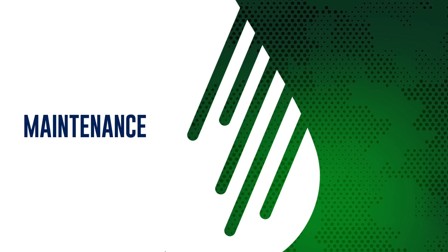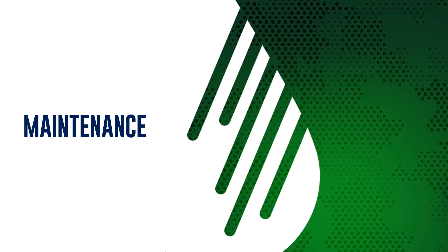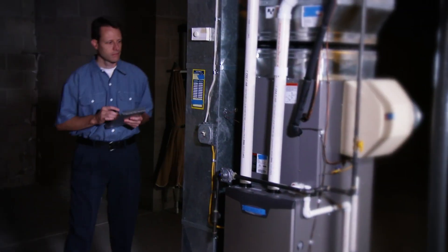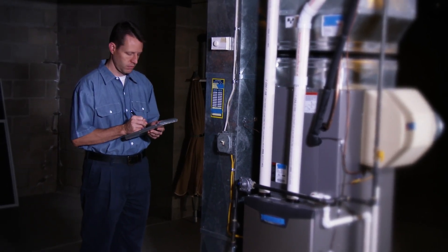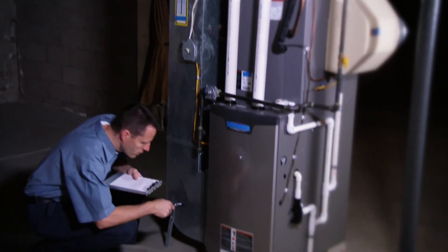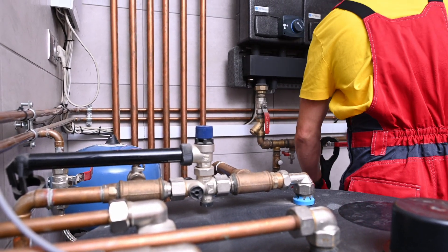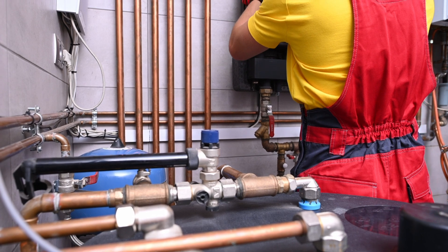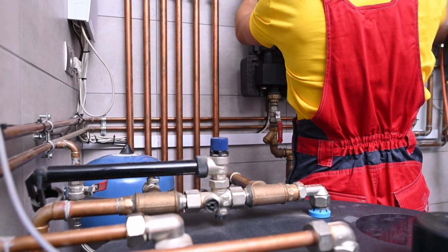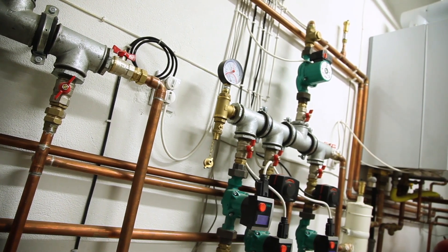A properly installed condensate neutralizer can perform effectively in high-efficiency installations for years, provided the device is routinely inspected and its neutralizing media — like JJM's proprietary pH power pellets — is replaced regularly. Although every boiler is different, generally the neutralizer should be serviced at least every 12 months by inspecting the device and replacing the neutralizing media. Best-in-class installers and service technicians will include neutralizer maintenance in the preventative maintenance program performed on the heating appliances. Over time, not maintaining a neutralizer is equivalent to not having one to begin with. Maintain that protection and stay on the right side of the plumbing codes.